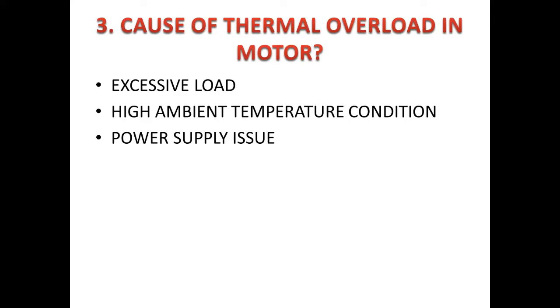The next question is the causes of thermal overload in a motor. The first one is excess load. When you are operating the motor, you must know the maximum torque the motor can withstand. If you give more load to the motor, it will increase the thermal value of the motor and affect the motor's life. Next is high ambient temperature condition. The motor is going to operate mostly in very rough areas, such as in a mine, deep inside where we cannot export air conditioning or a cooling system. In that condition the motor also runs, making additional heat.